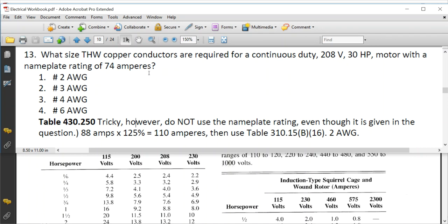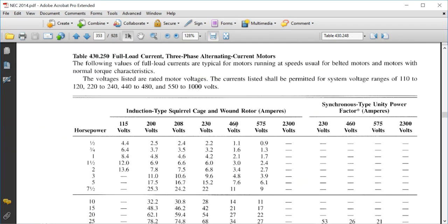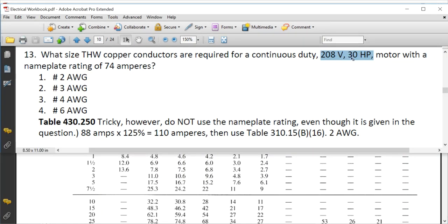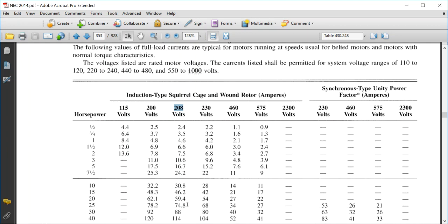The conductors are NOT based on the nameplate rating. The conductors — branch conductors or feeders — are based on the tables. Go to Table 430.250 for three-phase motors. Look up 208-volt column and 30 horsepower: the full load current is 88 amps. Write that down.